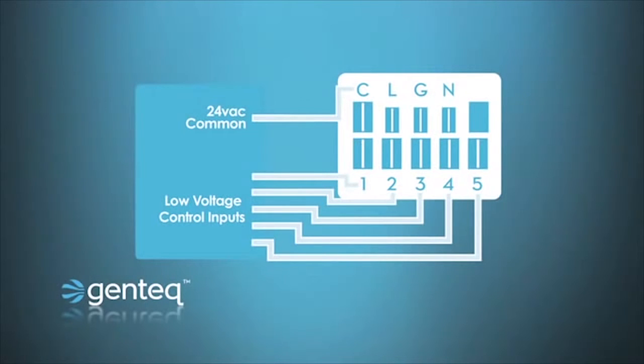Now I should also mention that these taps are 24 volts. Almost all manufacturers to date are using 24 volts for communication. However, there is the option to use DC communication. So in 24 volts, for example, if tap 1 had a program in it, I would apply 24 volts to tap 1, and right above that tap, the motor would read that voltage back on common. So all of the taps 1 through 5 are going to reference the common tap, which is a low voltage tap that's in the upper portion of the plug.